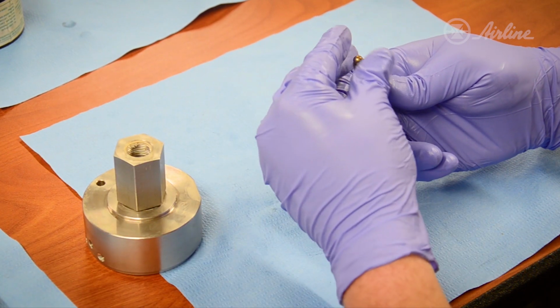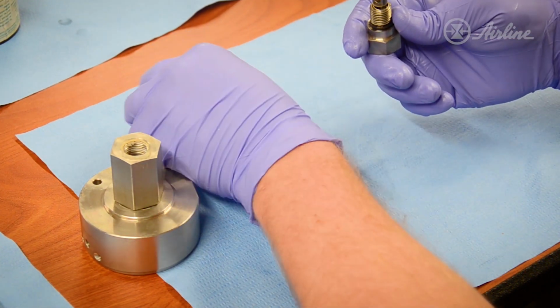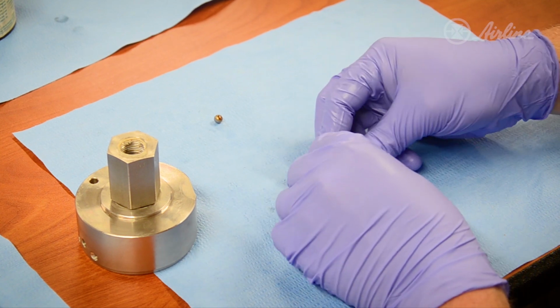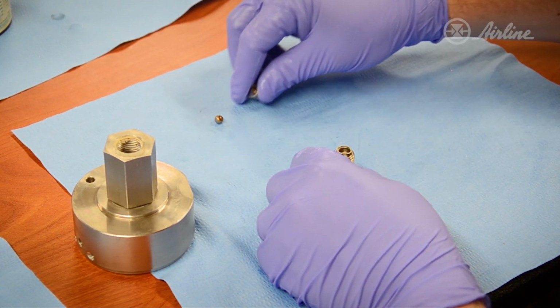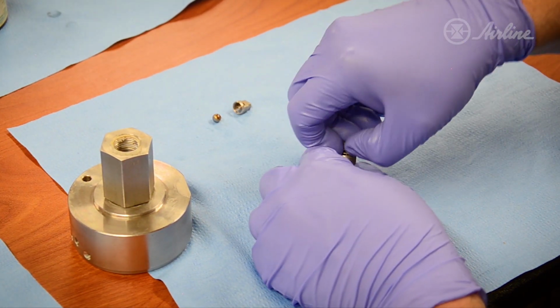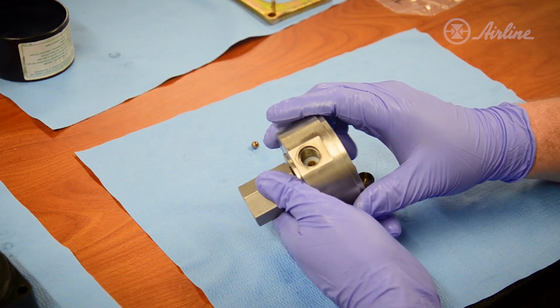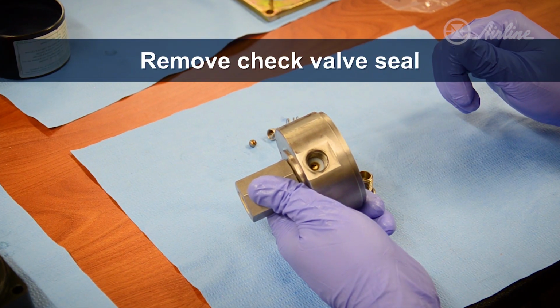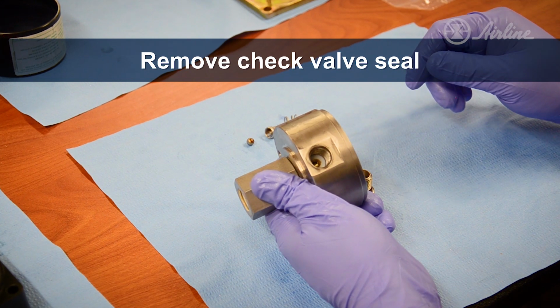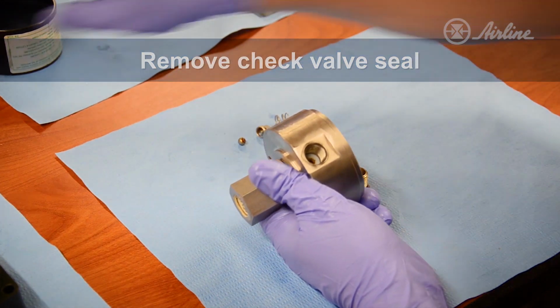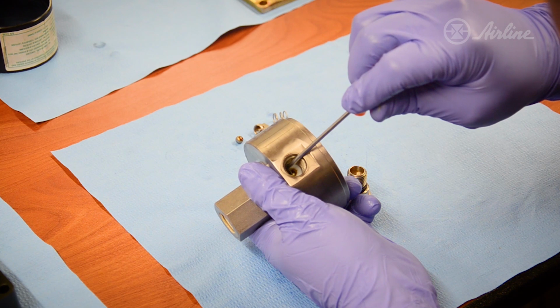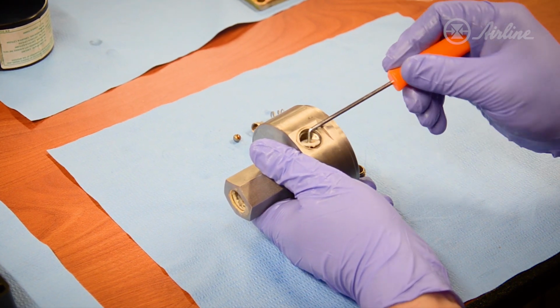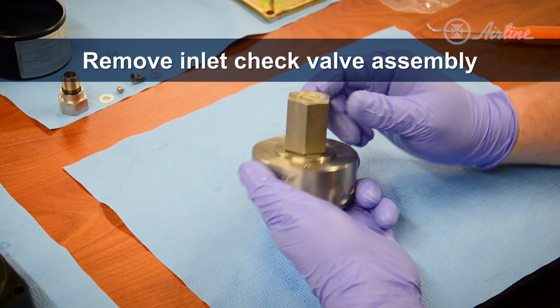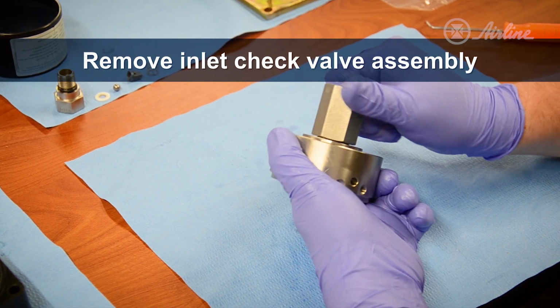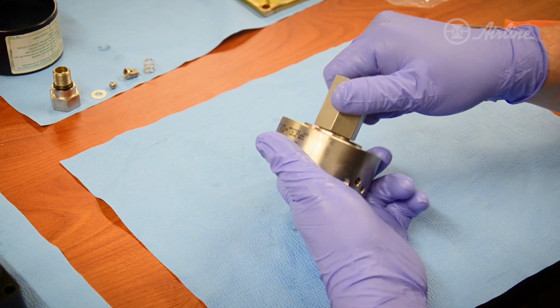We want to take care to keep all of these in the correct order. In the base of this port is the check valve seal, which we'll need to pick out and replace from our seal kit. So now we'll remove the inlet check valve assembly, which will give us access to the actual plunger seals on the pump.